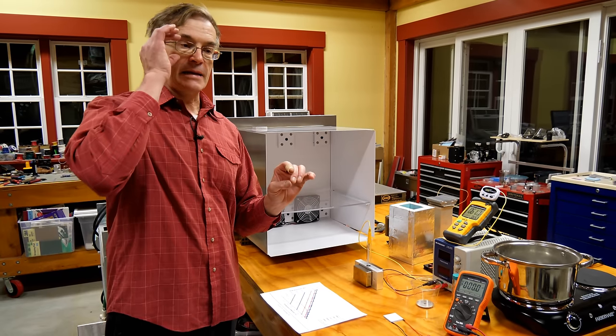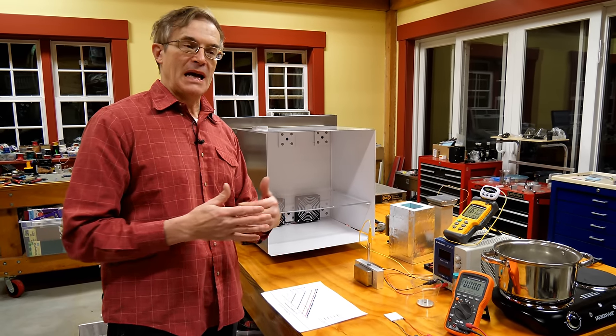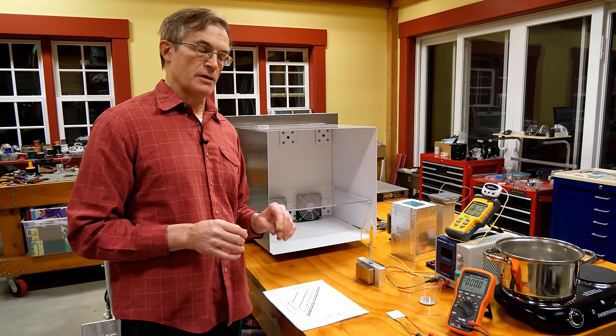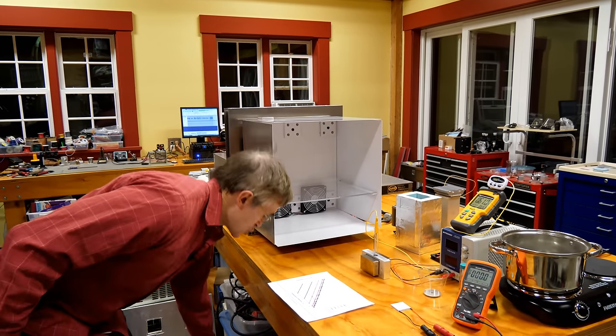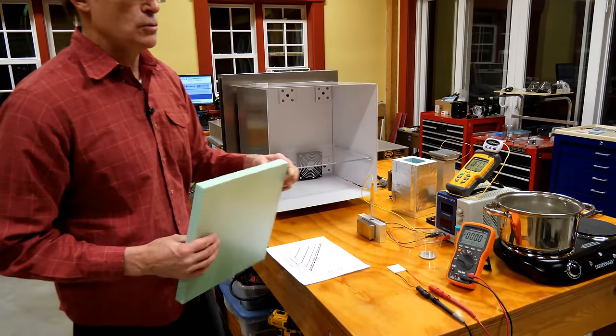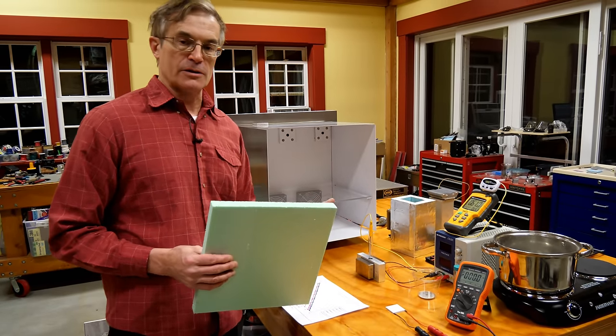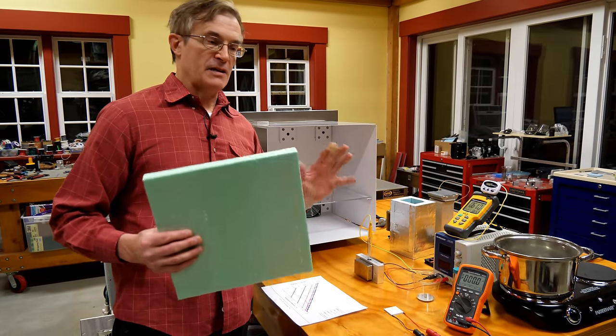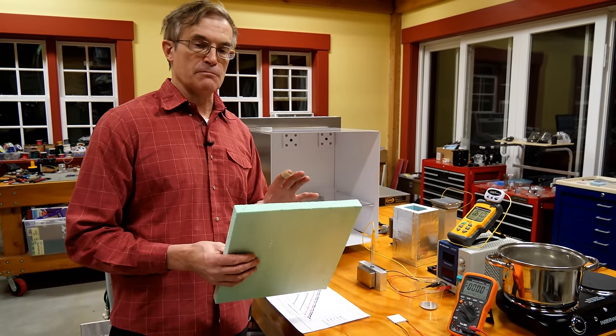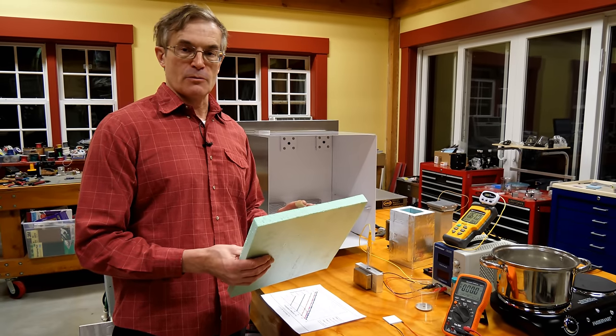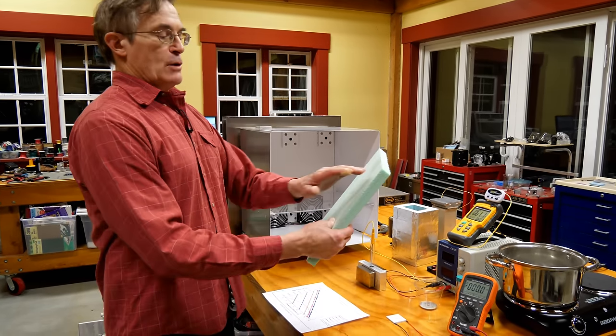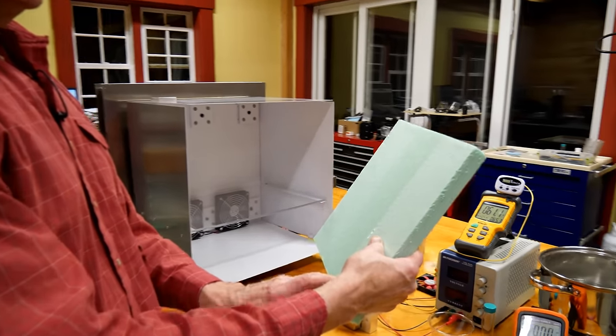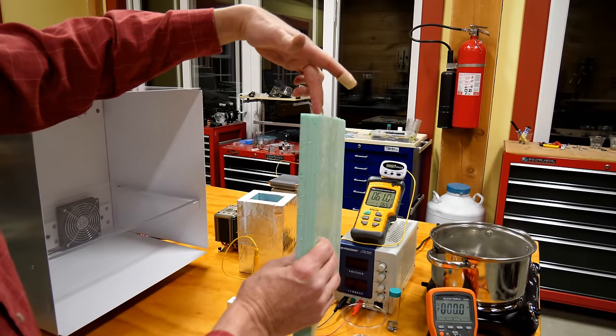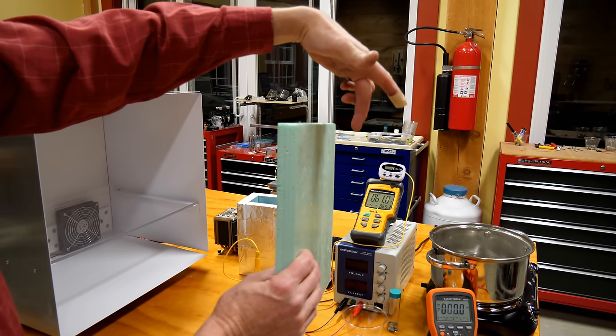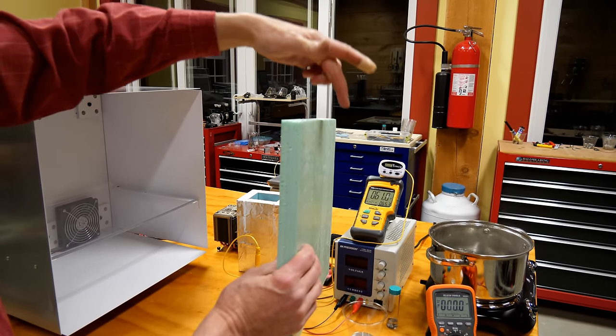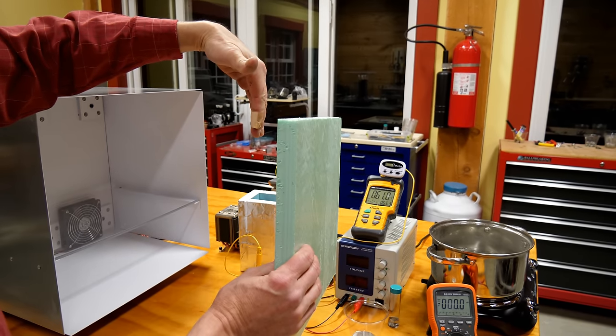Polyurethane has a 25% better blockage of heat flow, and so we're going to stick with that material. Now, the way that this material is described in terms of its ability to resist heat flow is called an R value. And for you metric people out there, I'm going to have to ask you to get out your conversion tables, because this is a completely imperial system of measurement, but it's pretty easy to remember. A 1 square foot piece, 1 inch thick of your insulation, will flow 1 BTU per hour per 1 degree Fahrenheit differential between the two surfaces.